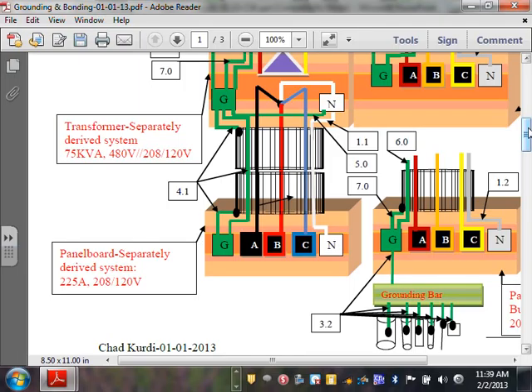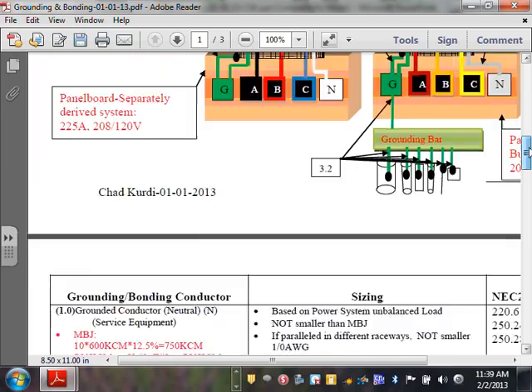If it's supply side bonding jumper, how do you size supply side bonding jumper? Based on the conductors that are coming out of the transformer. You basically, this number 4 and this number 5 are identical. A system bonding jumper and the supply side bonding jumper are identical in terms of sizing. How do we size them? We size it based on the conductor coming out. And if your conductors, per 250.66, are higher than 1100 kcmil, what do you do? That magic 12.5%. Okay, so I'm going to take you guys down all the way to 4.1.